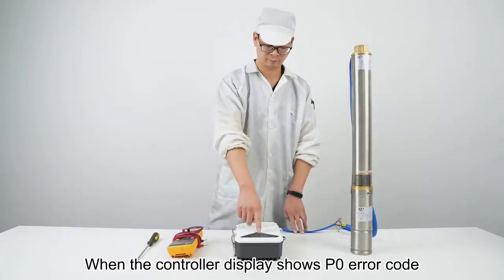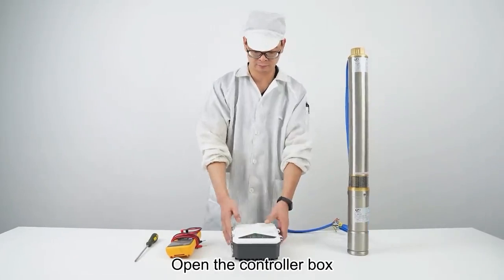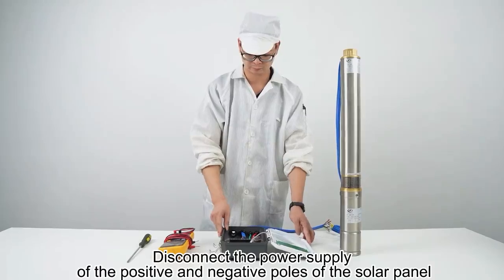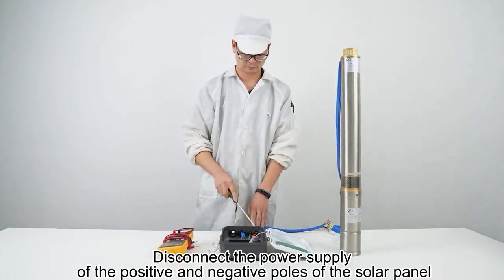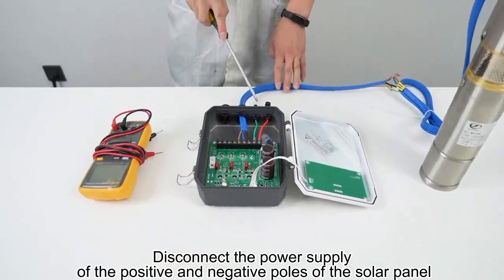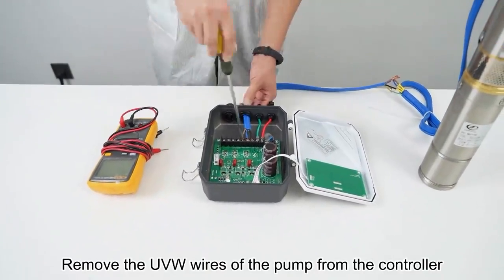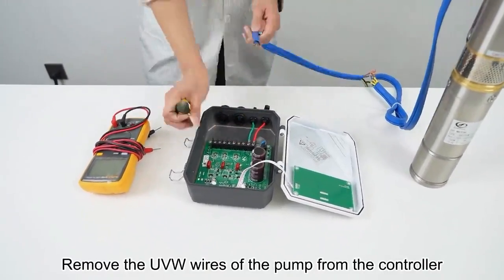When the controller display shows the P0 error code, open the controller box. Disconnect the power supply of the positive and negative poles of the solar panel. Remove the UVW wires of the pump from the controller.